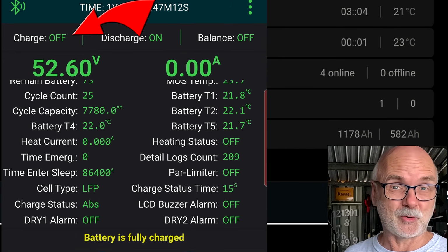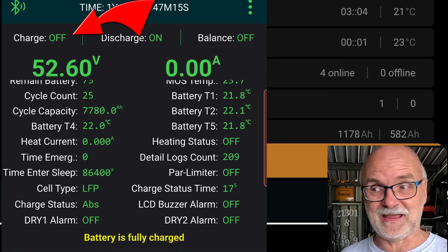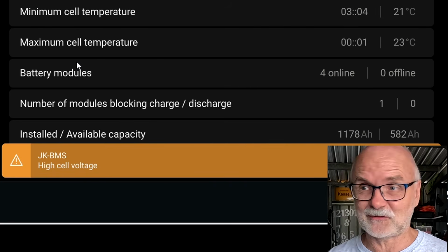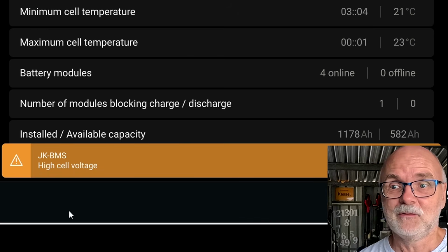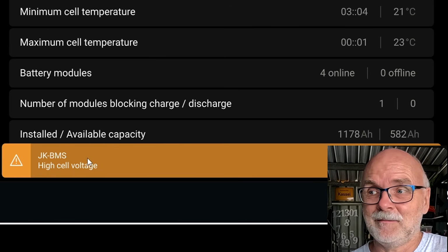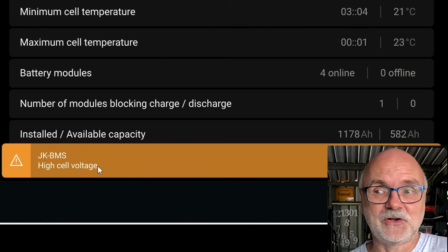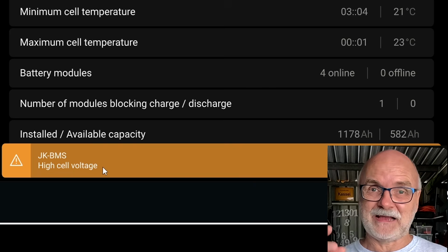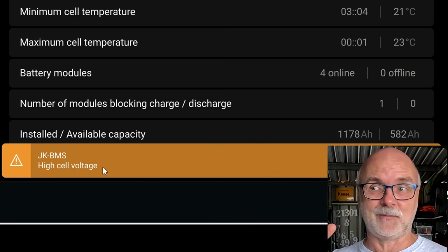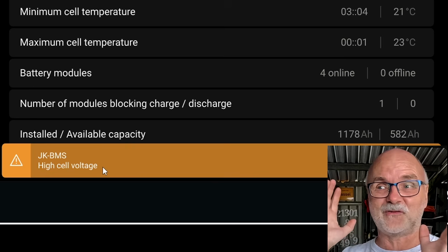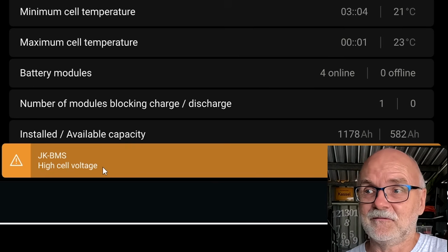So this BMS is now protecting your battery and keeps it safe. At the same time, you can see here in the Victron system or on your inverter, we've got a JK-BMS alarm: high cell voltage. Yeah, the master BMS has recognized, hey, there's something wrong with my slave number 3 and is reporting this all now to the inverter.